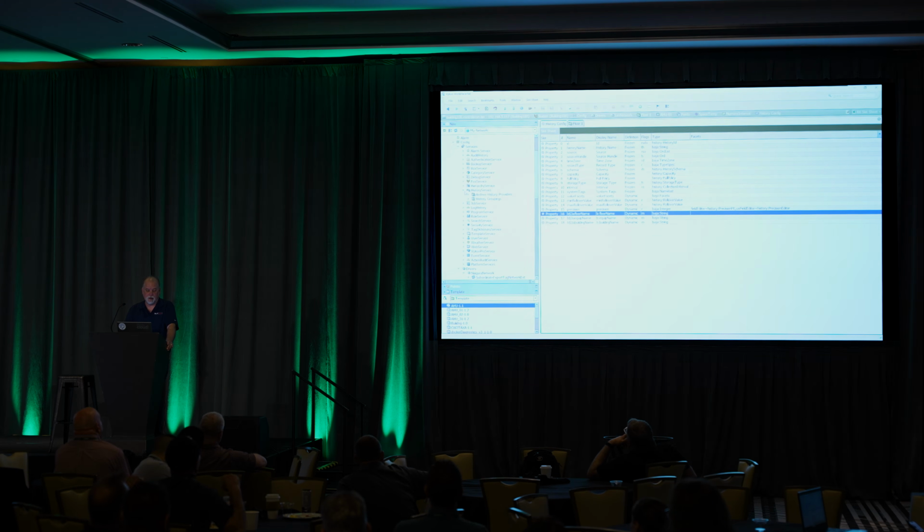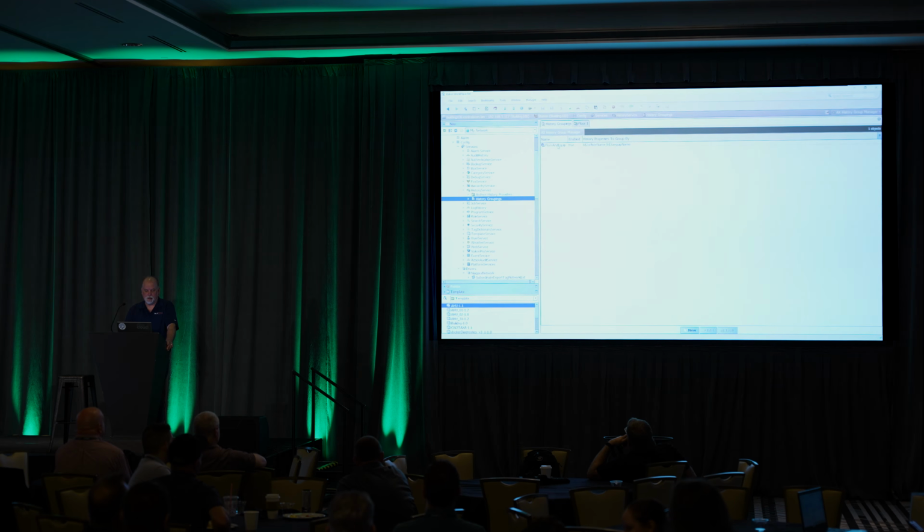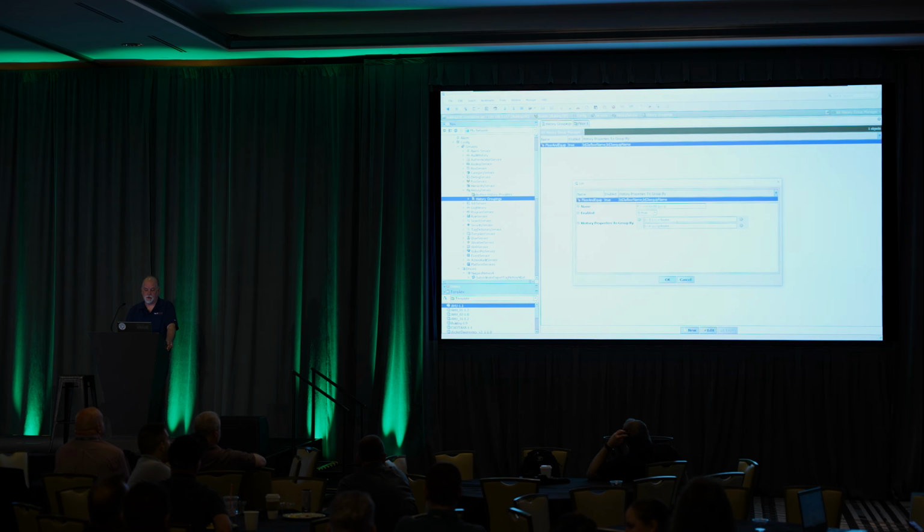So if I look at my history groupings in this case, I created a history grouping, and you can see that I grouped by my B: floor name tag and then my B: equip name tag. So you can use direct tags that you assign to the history configs to build your history groupings out. They can be the actual metadata tags that we were talking about here with Niagara 4 compared to AX.